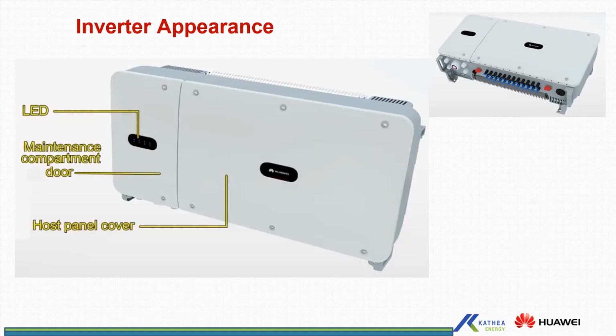All our inverters have 3 LEDs on the screen. The first one symbolizes DC. If your inverter is connected to DC power, it will illuminate, symbolized with a straight line. So it's just an LED indication with a straight line. The second LED is for AC synchronization. When the inverter is successfully synchronized with your grid, that is, if your grid is within the NRS parameters for South Africa and the Southern African region, when the inverter synchronizes and accepts the grid, it will illuminate the LED. It has a sinusoidal indication.